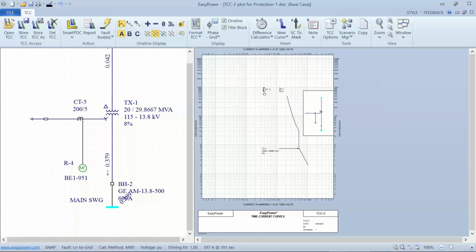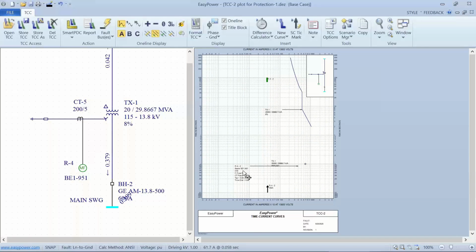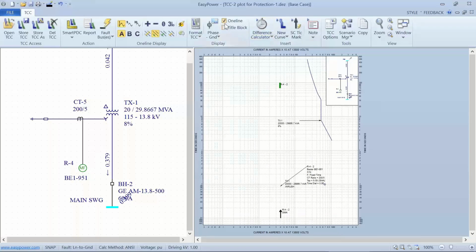And what we're looking at is this current right there, which gives me, let's see if I got this right. I'm on the 13.8 scale times 10. There's my max 399 on R4-2. So anything above that will be a fault.